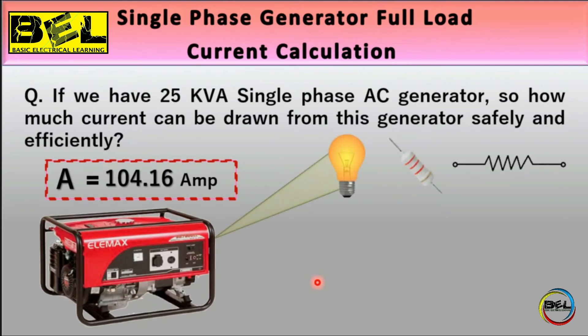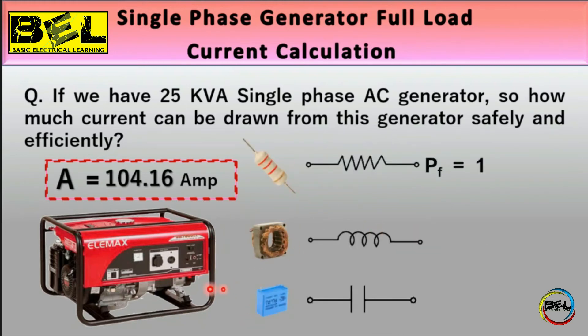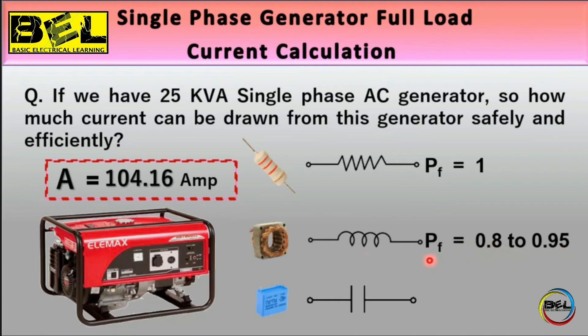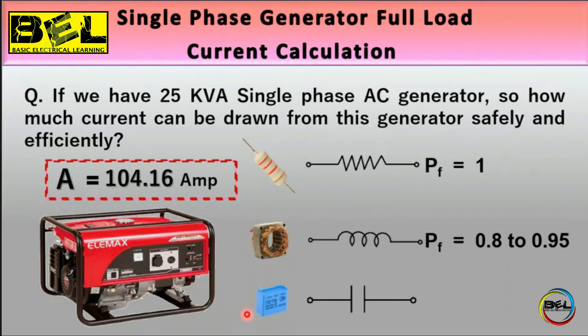Generators have different types of loads: resistive, inductive, and capacitive. The power factor for a purely resistive load is 1, and for a purely inductive load it is 0. For a combined resistive and inductive load, the power factor becomes 0.8. Since an AC generator typically has capacitive, inductive, and resistive loads combined, the effective power factor is approximately 0.8 to 0.95. We must include the power factor in our current calculation.